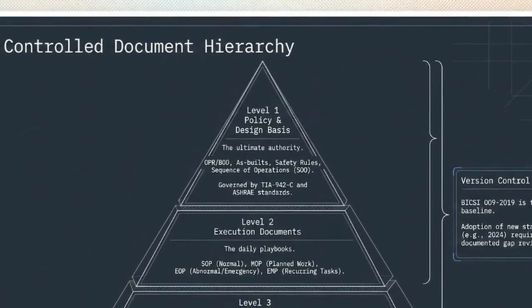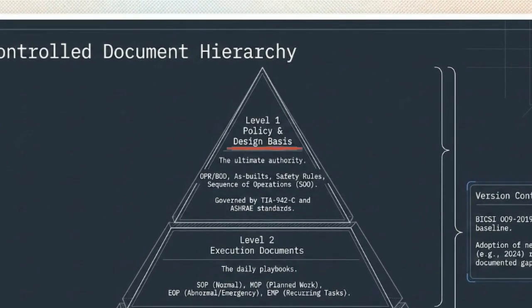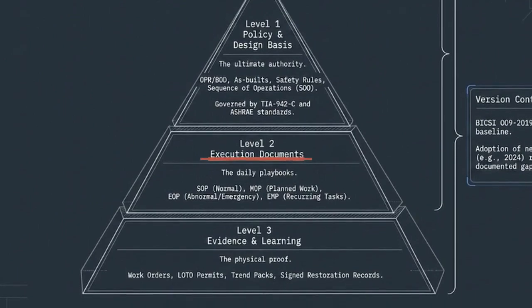This pyramid dictates exactly what operational conditions are allowed, starting from the foundational design basis at the top. The middle tier defines the daily execution documents. Operators use standard operating procedures for normal, repeatable tasks, methods of procedure for planned work, emergency operating procedures for abnormal events, and equipment maintenance plans for recurring physical upkeep.